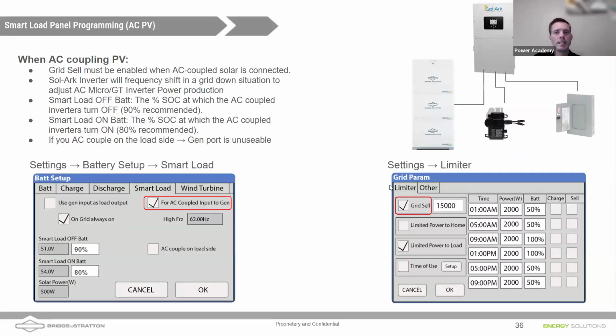Okay, when we are programming AC coupled solar, we're going to come into the smart load tab under battery setup. So go to settings and then battery setup and smart loads. And you want to make sure you have this box checked for AC coupled solar input to the gen port. And then your customer is going to want to sell any excess. I'm assuming they had an interconnection agreement. So this will keep the AC coupled solar on as long as the grid is on, having this box checked. So you want to have that box checked for on grid, always on, unless you have some reason why you don't want that AC coupled solar pumping when the grid is there.